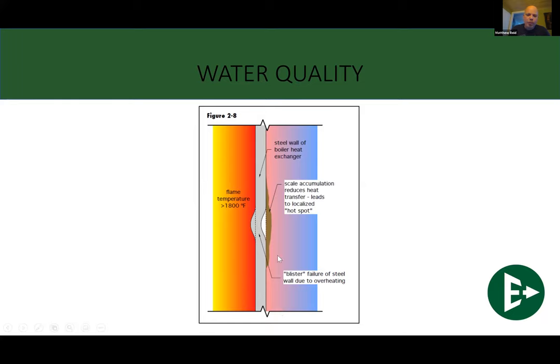We have scale that builds up inside the water side of that heat exchanger. And then we have flame, fire, be it oil, propane, natural gas, I don't care what it is, you're going to have a heat source on the other side. If I can't scrub that heat away, I'm going to blister that metal. Once I start blistering it, I start really stressing out that metal, and eventually over time, it's absolutely going to lead to a crack. Once it gets that hot spot and it blisters up, you're going to be cracking there. That's what's going to happen.